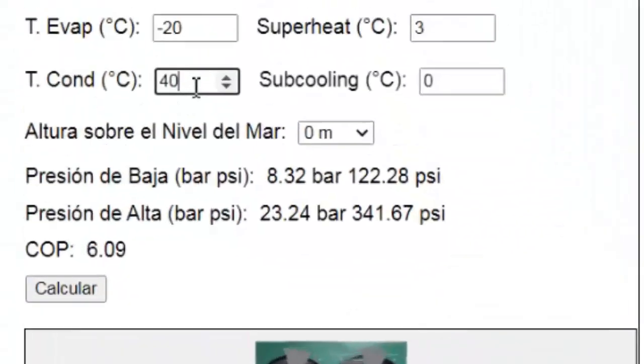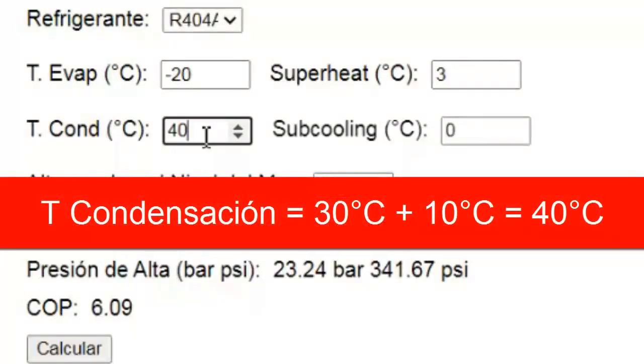To calculate the condensation temperature within the refrigeration system, we will add 10 degrees Celsius to the ambient temperature surrounding the equipment. For example, if the ambient temperature is 30 degrees Celsius, the condensation temperature will be 40 degrees Celsius.